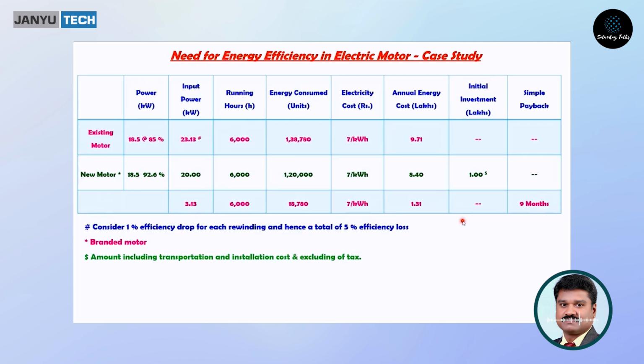So 18.5 divided by 0.8, 80% is 0.8, so it will take 23.13 kilowatt at full load condition. Whereas the new motor, 18.5 kilowatt divided by 0.926, will take only 20 kilowatt. So if you replace the old motor with a new motor, the saving is going to be 3.13 kilowatt. The running hours per annum is going to be 6,000. So 3.13 into hours will save nearly 19,000 kilowatt hours, 19,000 units. If the cost of electricity in that particular area is 7 rupees per kilowatt hour, then your cost saving is 1.3 lakh.